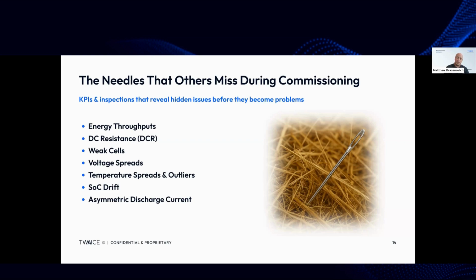For example, we look at different KPIs, energy throughput being the most basic one. We look at that not only at the system level, but at the component level across the system to see if everything is being discharged equally. We look at DC resistance, looking at what the voltage drop is under a current pulse for different parts in the system, potentially highlighting things like loose interconnects.